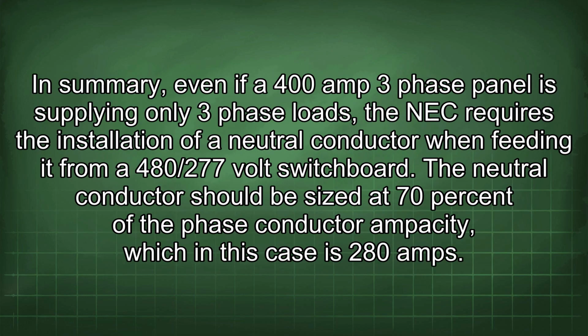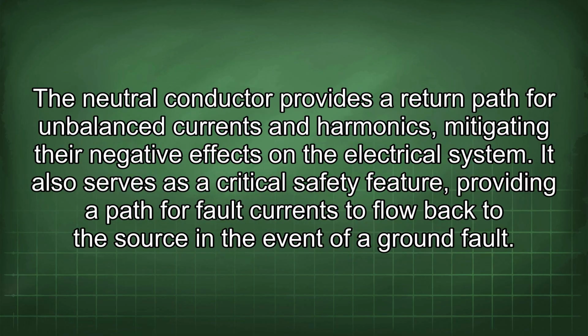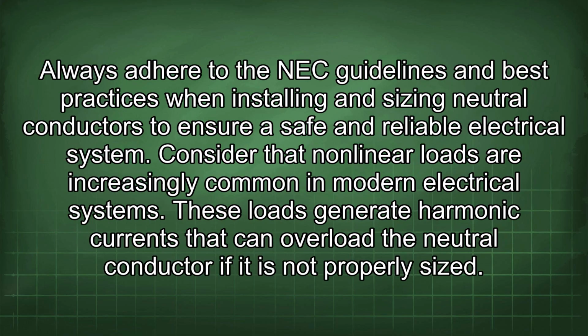In summary, even if a 400 amp 3-phase panel is supplying only 3-phase loads, the NEC requires the installation of a neutral conductor when feeding it from a 480/277 volt switchboard. The neutral conductor should be sized at 70% of the phase conductor ampacity, which in this case is 280 amps. The neutral conductor provides a return path for unbalanced currents and harmonics, mitigating their negative effects on the electrical system. It also serves as a critical safety feature, providing a path for fault currents to flow back to the source in the event of a ground fault. Always adhere to the NEC guidelines and best practices when installing and sizing neutral conductors to ensure a safe and reliable electrical system.